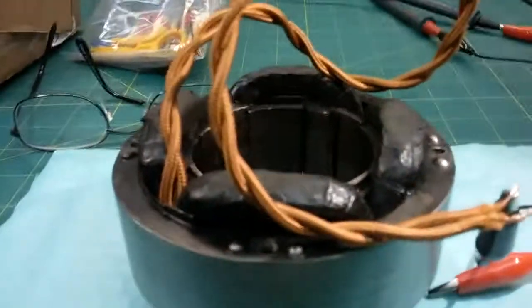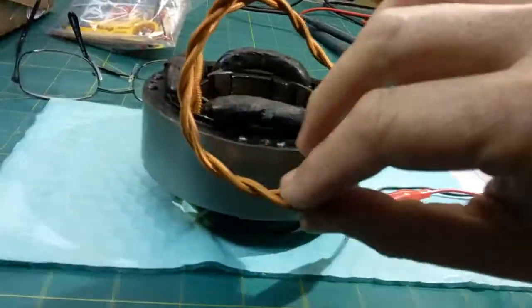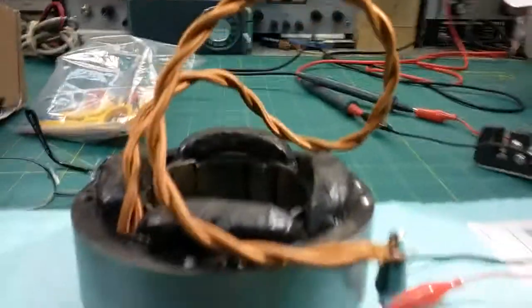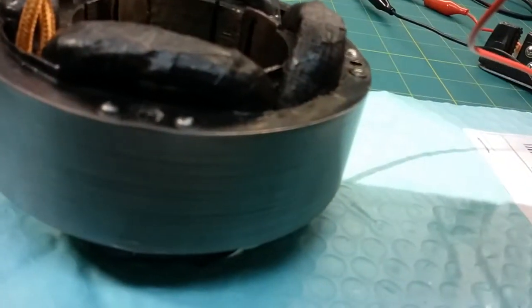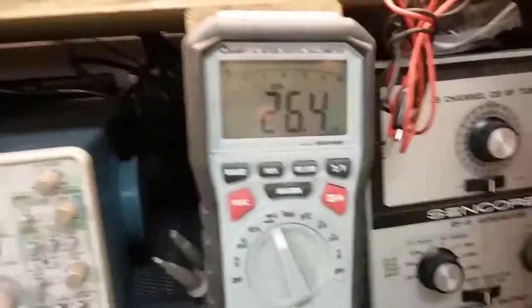So how do you check out a stator when you don't have the armature of the motor? That's a good question, and I'm going to show you how to do that. In this case, I've already connected the lead wire, so I'm going to check the resistance across the coil via the alligator clips and my digital multimeter.